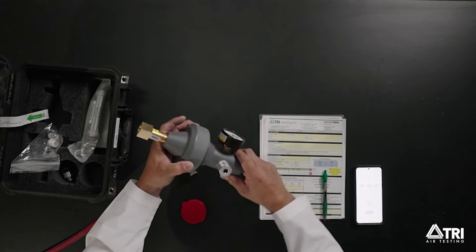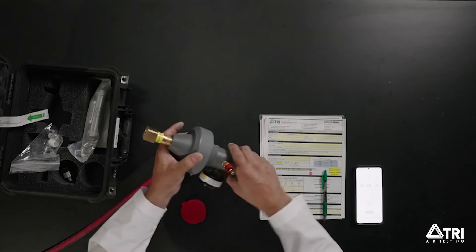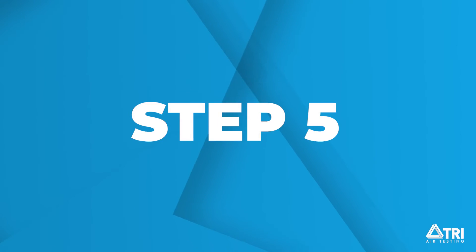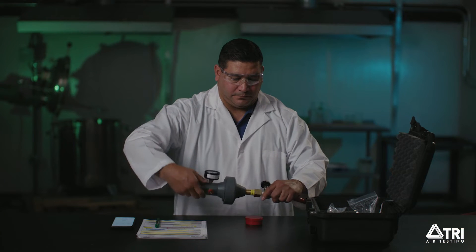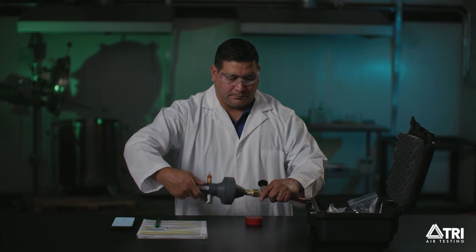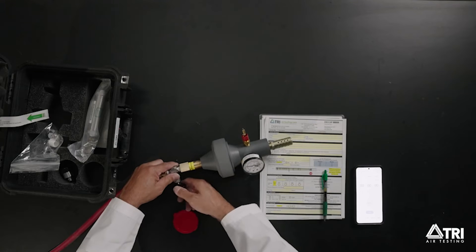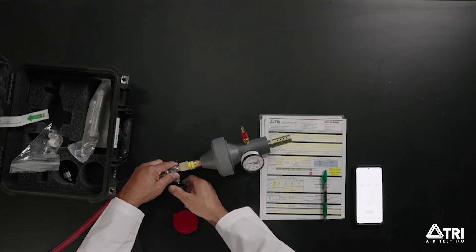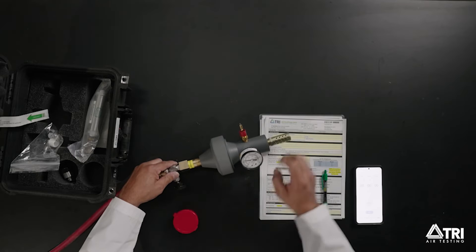Step 5: Connect the complete unit to your gas source. Open the gas source valve slowly and allow the pressure on the flow section gauge to stabilize in the specified PSI range. Run the sample according to the time specified on your instruction sheet.